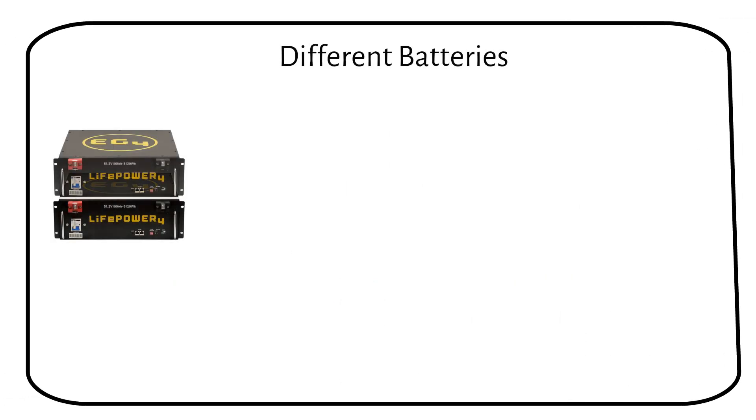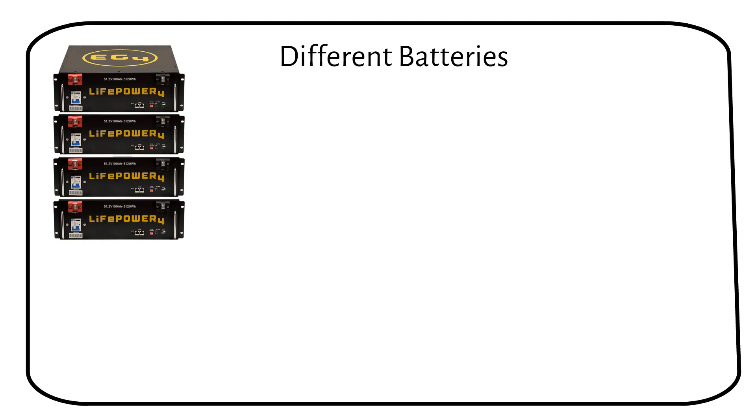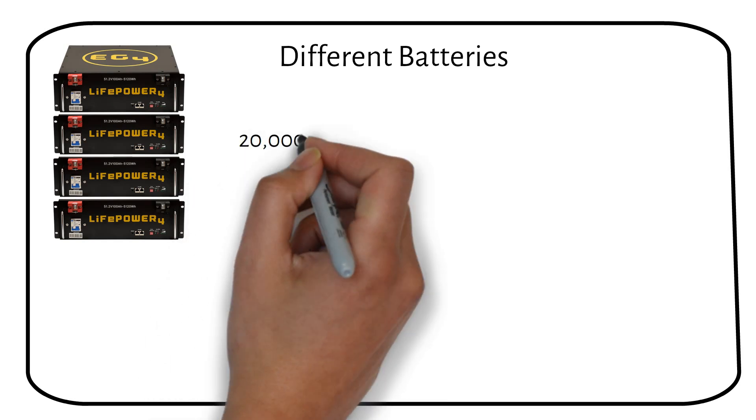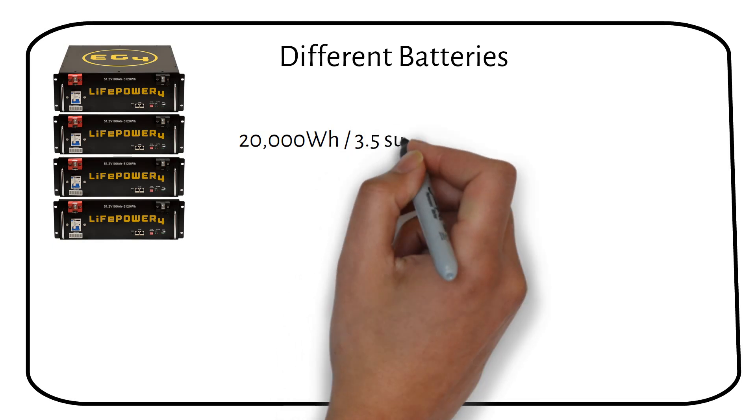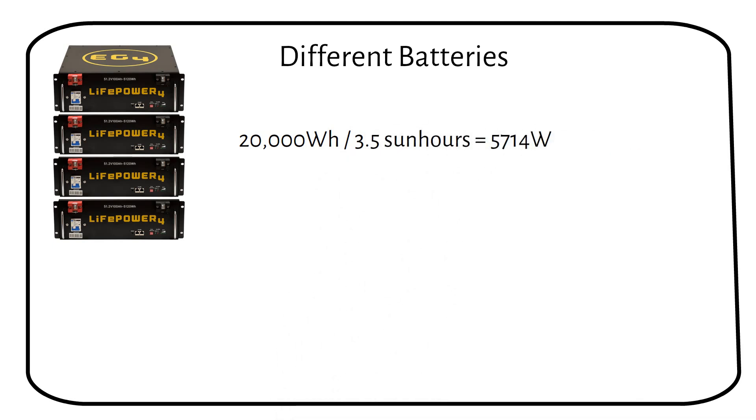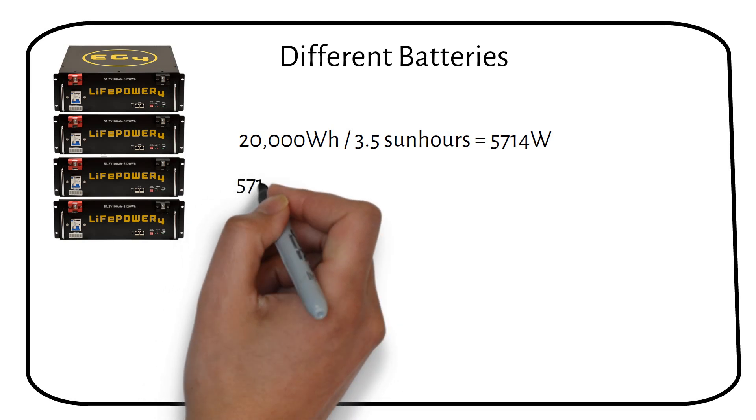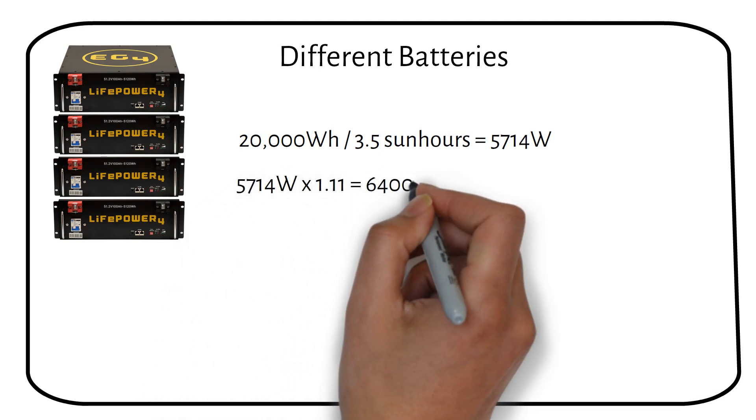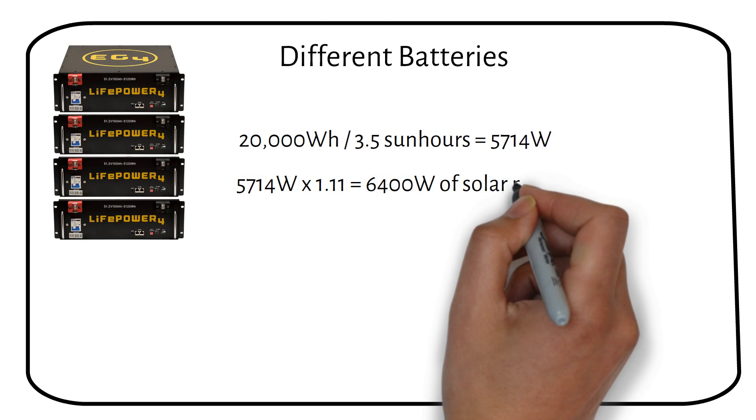Now let's calculate for different sized batteries. Let's say you have 4 server rack batteries totaling 20 kilowatt hours. To recharge this battery in one day, you need to follow the same calculation process. 20,000 watt hours divided by 3.5 sun hours equals 5,714 watts. Then multiplying by the safety factor, we get 6,400 watts of solar panels.